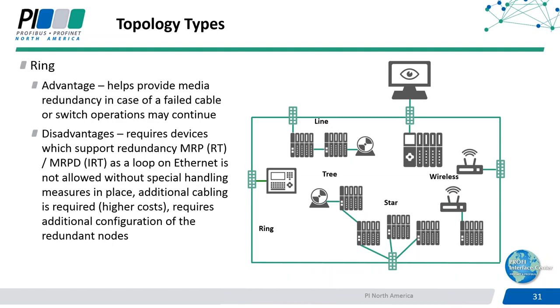On PROFINET, these are optional features, and we call that MRP or MRPD, and would require all the nodes in the ring to support that function. In addition, a disadvantage to redundancy is that you have to plan for it, and it's going to require some additional cost and configuration to install and set up.